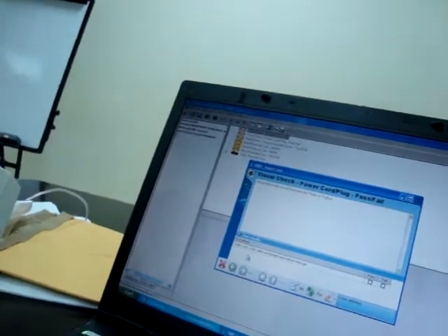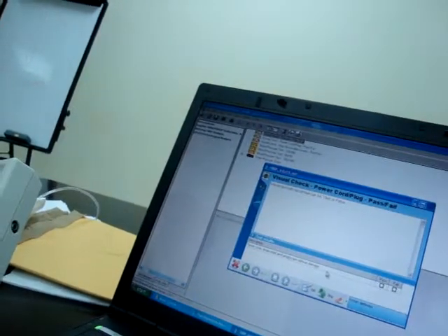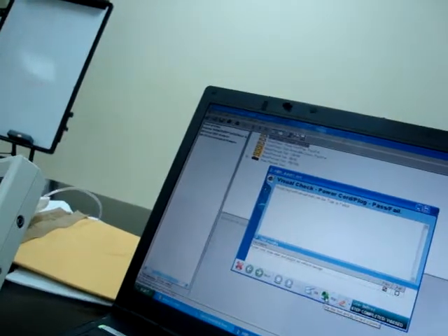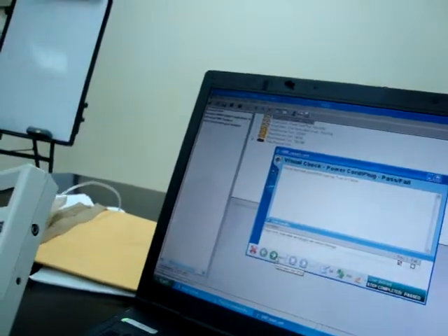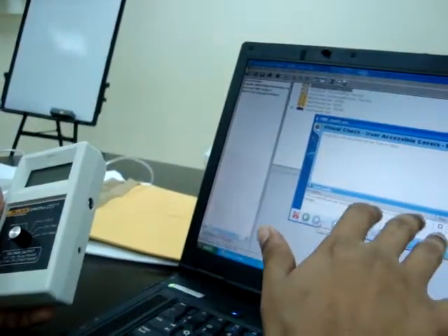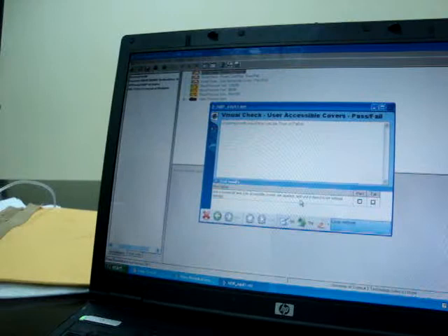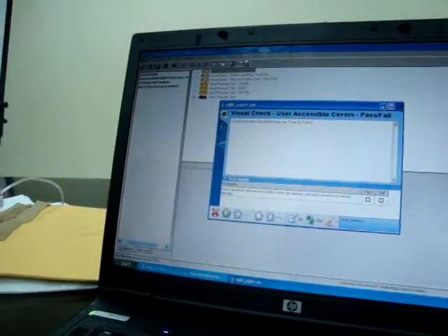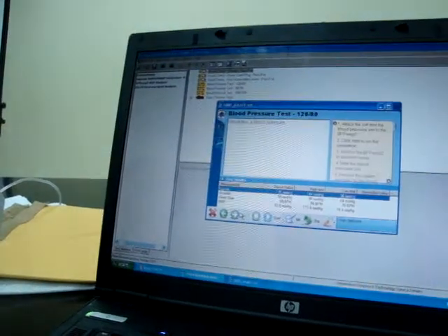Then it shows power cord. Is the power cord there without any damage? Yes, pass. Okay. Or if you want, you can skip this step. This is to do the report. Exactly for the report. You can write in your own words if anything. Okay. Unit is turned off and user accessible covers are open, and unit found to be without damage. Okay, these are all simple things, just like your own.